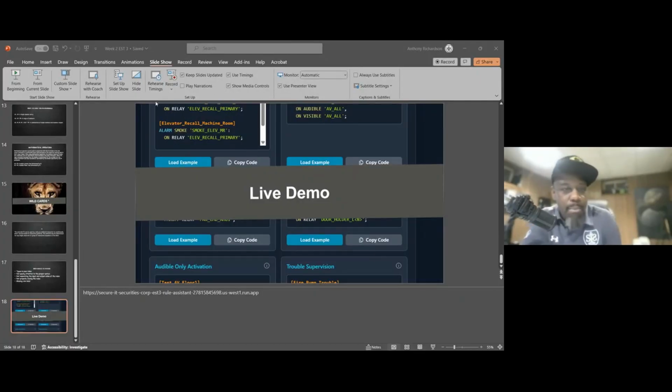So the object label text is pretty much already defined. When I come to the rules, edit rules. So level 1, I can't make this no bigger. So we have level 1, smoke 1. Actually, this would only set off 1 smoke detector, to tell you the truth. So I will have to put the wildcard star in order to make this go active.